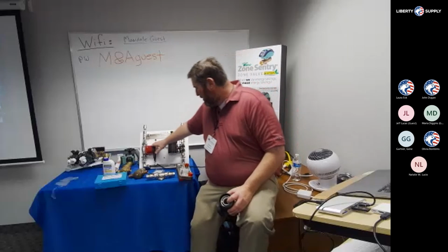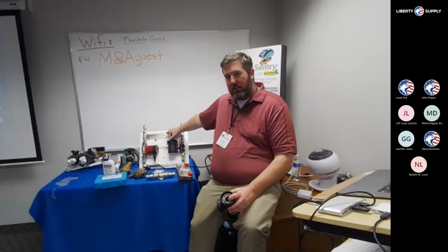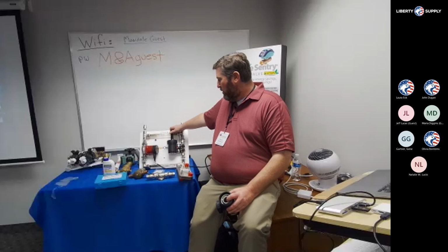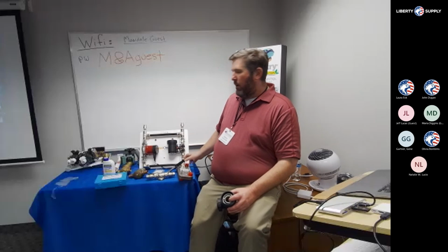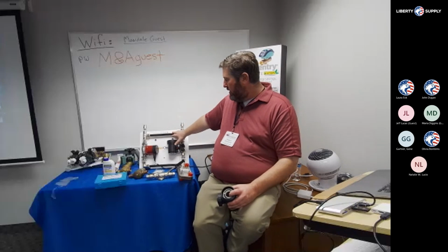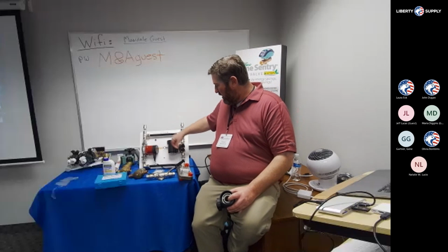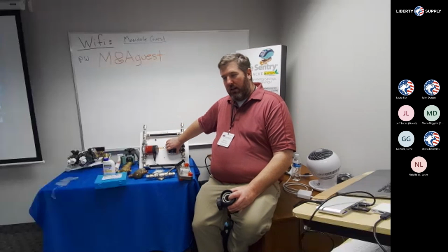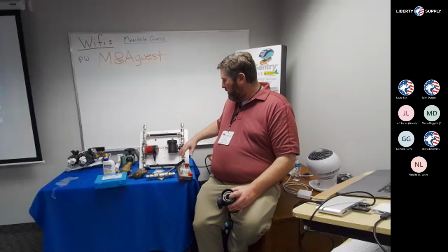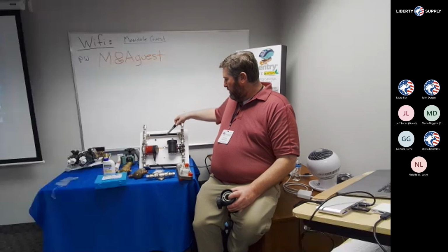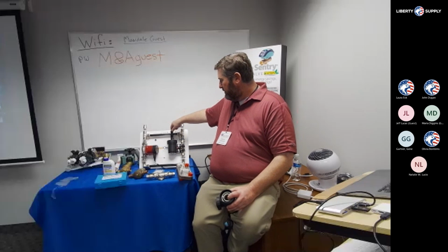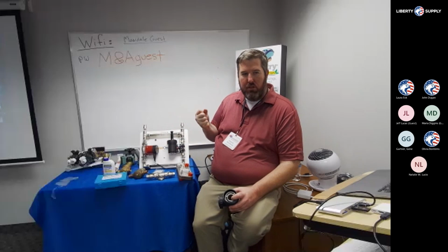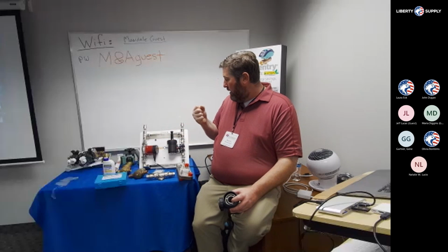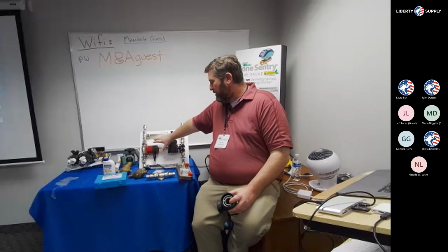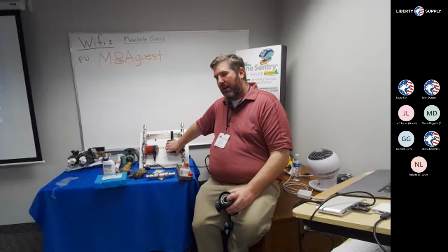We have an ECM pump, we have a magnetic filter, and there's some iron oxide built into that system. The whole point of this is to show a live running system of what it looks like. If I pull that magnet out, I can see the iron oxide leaving the filter, because right now it was being held captive in this filter in solution. As I pull that magnet out, you can see that it went back into that water source. If I put the magnet back into that system, you can see how that captures all of that sediment and that iron oxide back into the filter. We're going to hold it captive so it's not sitting in the pump. And now you can see that the water has cleaned itself up just from that simple ability of having this magnetic filter on site.